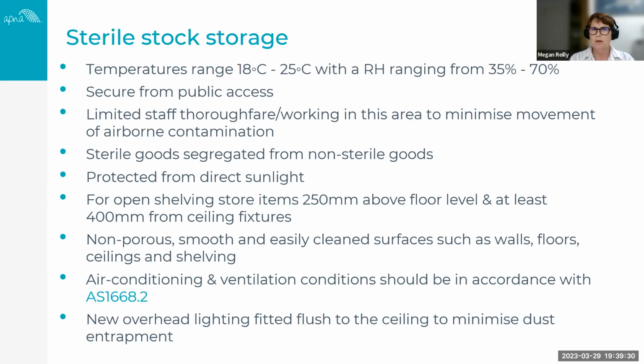Also, sometimes the questions that we get are around the safe storage times for sterile packs, and that can vary depending on the porosity of the wrapper and the storage conditions. So open versus closed containers, for example, or cabinets. So heat sealed, plastic peel-down pouches have been reported to remain sterile for as long as 9 months after sterilisation. But really what you need to ensure is that you have a process in place.